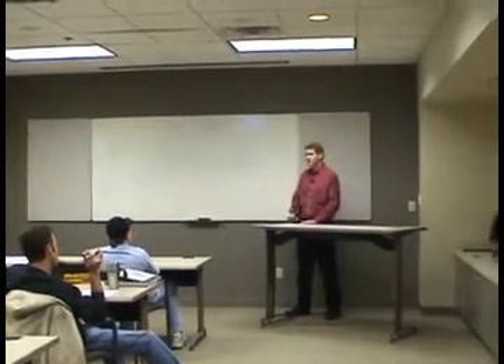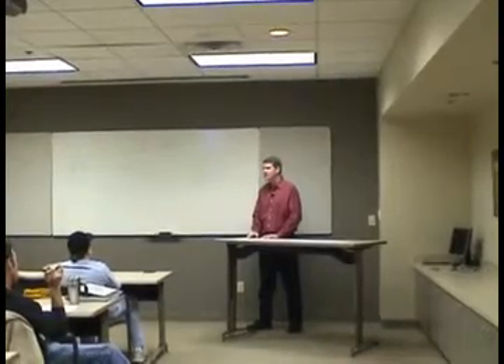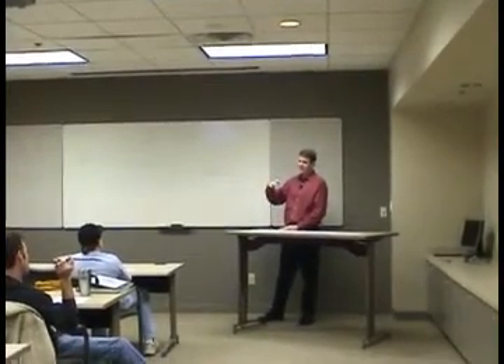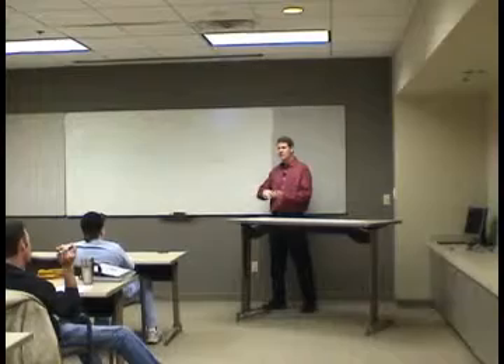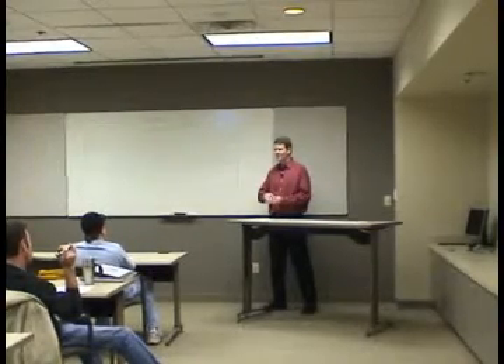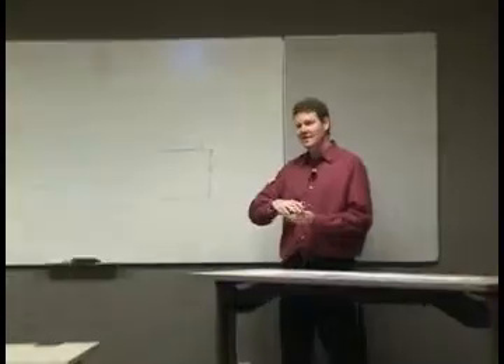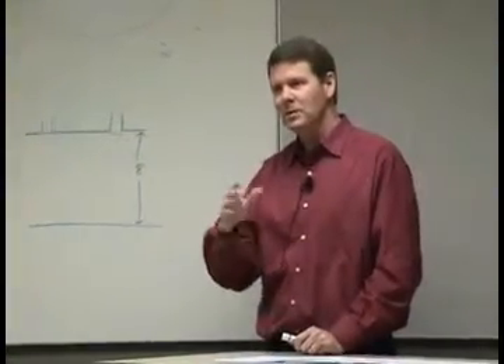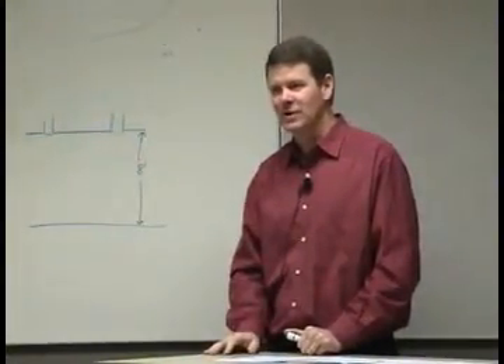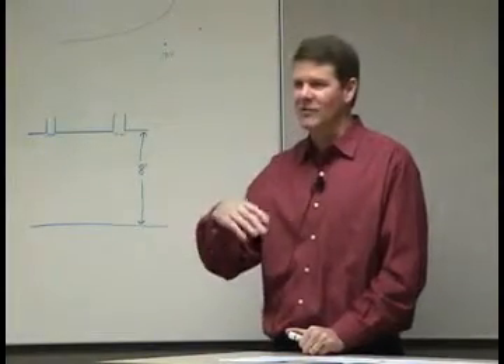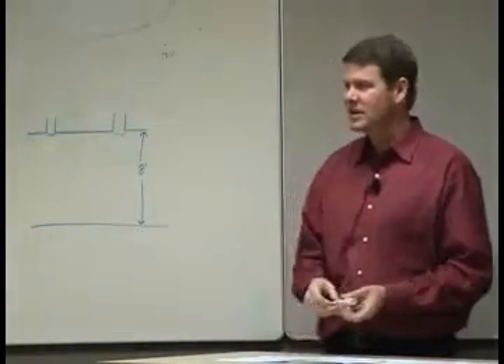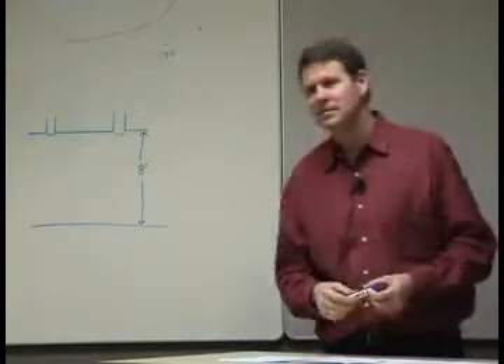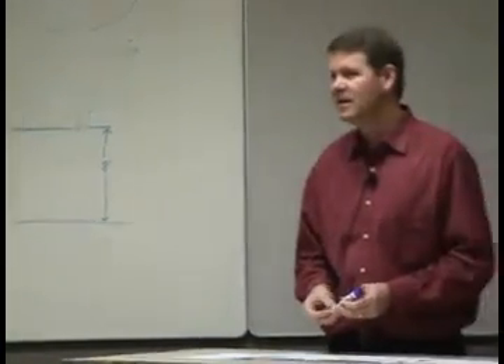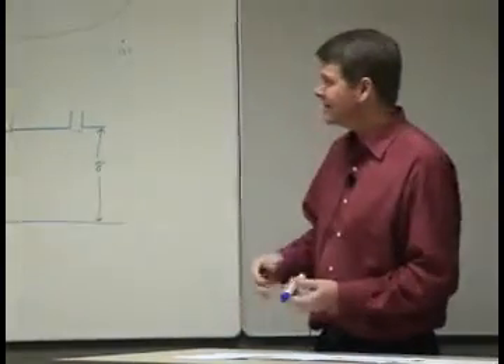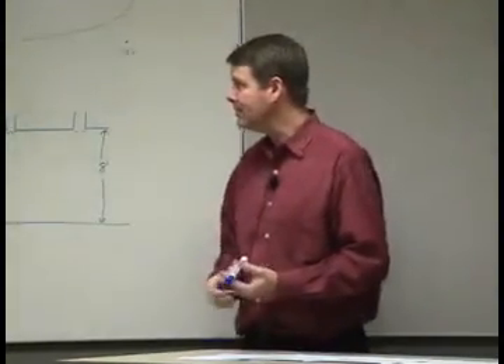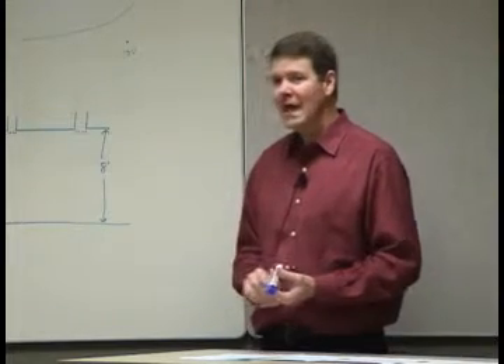We try and do it all the time. Realistically, we come down, the damper moves down a little bit, our reading drops to 0. Doesn't mean the flow drops to 0. We just can't read it anymore. We open it up a little bit, it comes back up on the scale, we read it a little more, we back off again. It's bouncing up and down. Nobody will probably ever notice, and it'll probably be fine. But we have a real accuracy problem, and we have another problem.